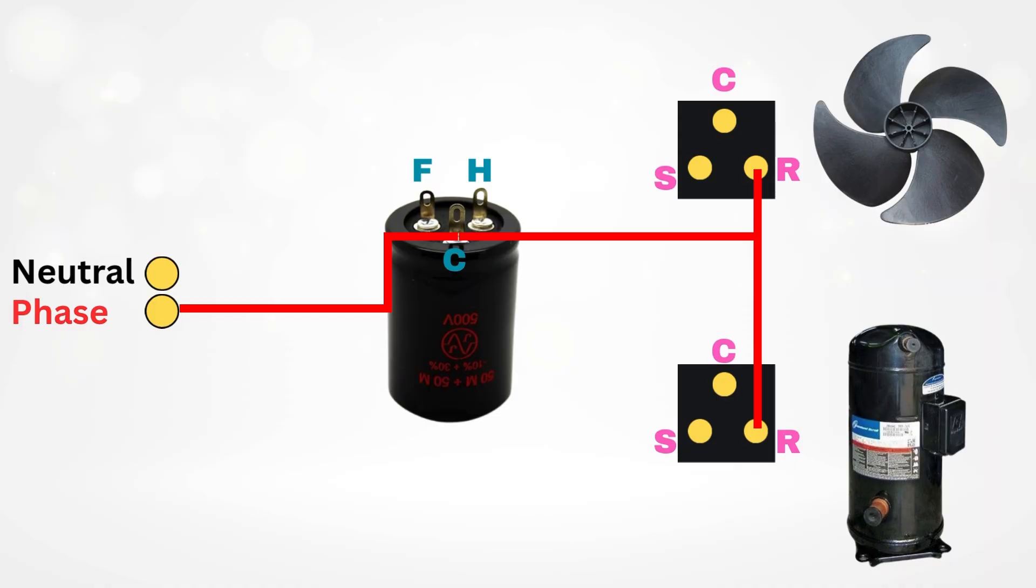Then, connect a wire from the fan terminal of the capacitor to the starting terminal of the fan motor. Similarly, connect another wire from the Herm terminal to the starting terminal of the compressor.